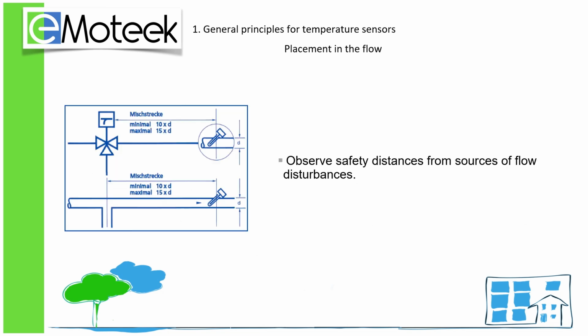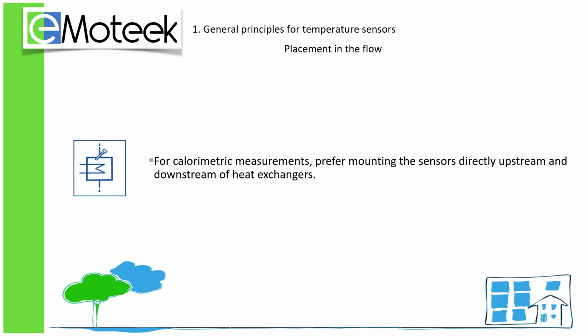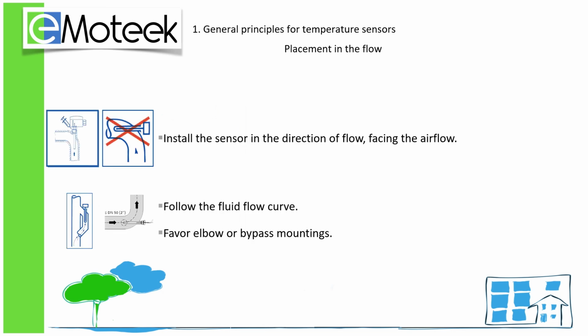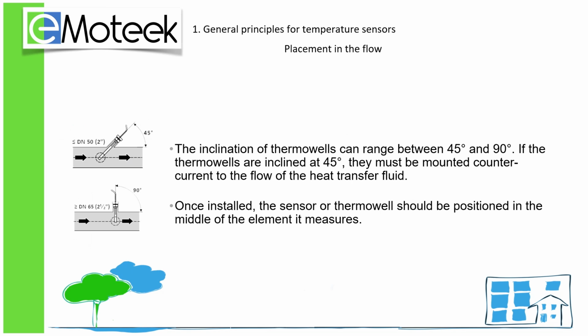Next, allow a distance of 10 to 15 times the pipe diameter downstream of any flow disturbance. For calorimetric measurements, use sensors both upstream and downstream of heat exchangers. Okay, I understand. Always install the sensor in the direction of flow, following the fluid's flow curve and favoring elbow or bypass mounts. The thermowells should be inclined between 45 degrees and 90 degrees, depending on the pipe diameter.